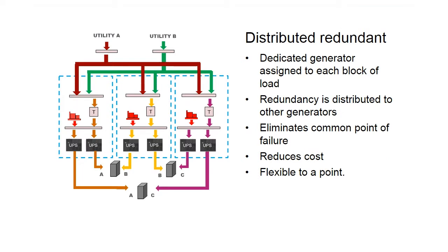The third is a distributed redundant system. Again, this uses a dedicated generator for a block of load, but what it does is build in the redundancy to the other systems. So your A system would then fail over to your B and C systems. It eliminates the common points of failure. It does reduce costs. The big problem with this is it's flexible to a point as you start getting to four generators. Three is commonly known as maybe three to make two. I've seen three to make four or four to make three, but as you get higher, it gets really difficult to manage load, so it's only flexible to a point.